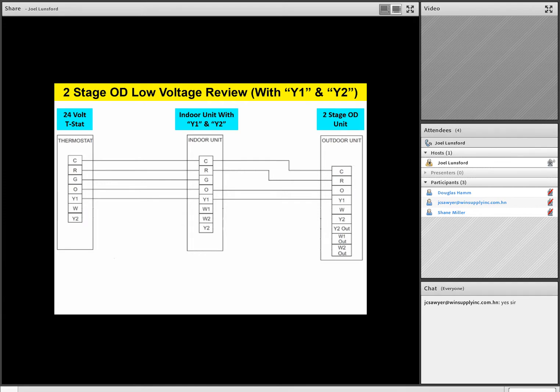The other thing I'd like to stress is that even though the TH16 is a 5-stage product, you wire it like a two-stage product. It's a conventional 24-volt unit. That little TH16, a 5-stage or 5-step heat pump, it's strictly 24-volt wiring. And the way you would wire that up, you'd actually wire it like a two-stage product outside. And then the outdoor unit makes some intelligent decisions on when to stage and how to stage from 50 to 100% capacity in 5 steps. So just kind of keep that in mind as well.